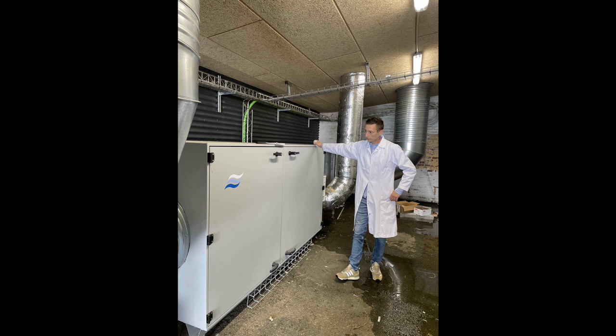In a cold store, there can be a lot of waste heat from the refrigeration process. A condenser coil expels the heat generated from the cold store's cooling system, and we can actually use this waste heat as an energy source for the dehumidifier's regeneration process. Now, in some cases, using this energy source alone can be enough to provide a good level of drying capacity and achieve a cold store's goals in removing excess moisture and preventing the ice or mist.